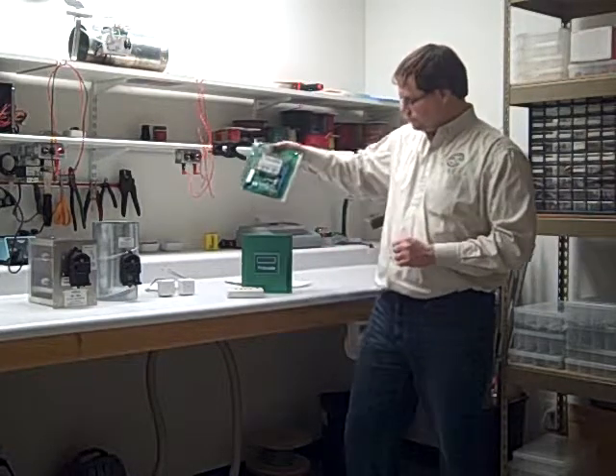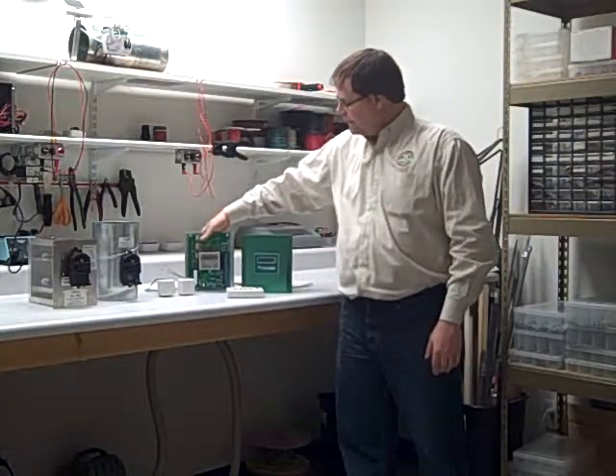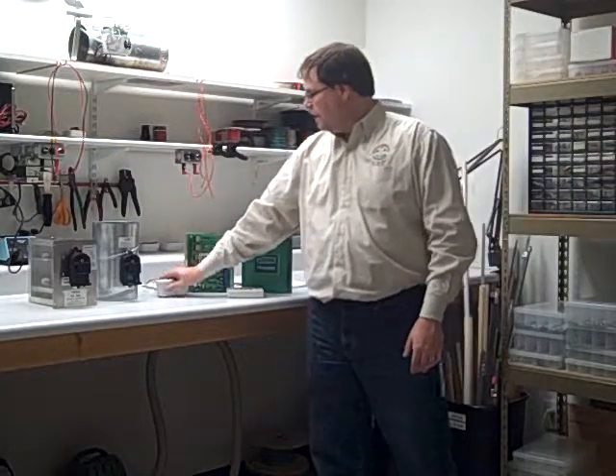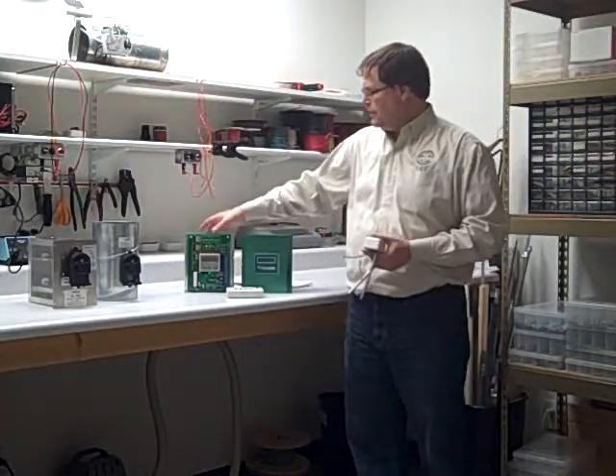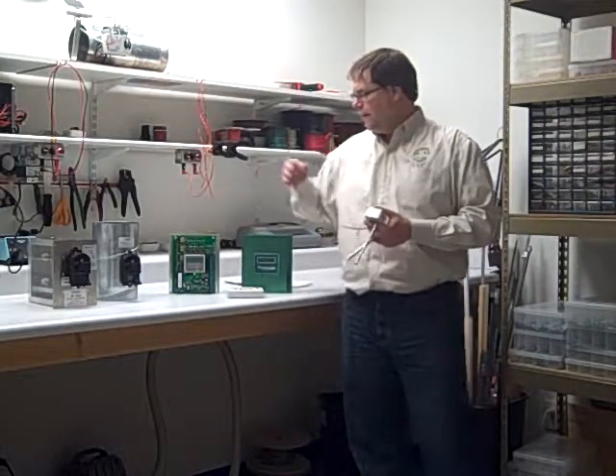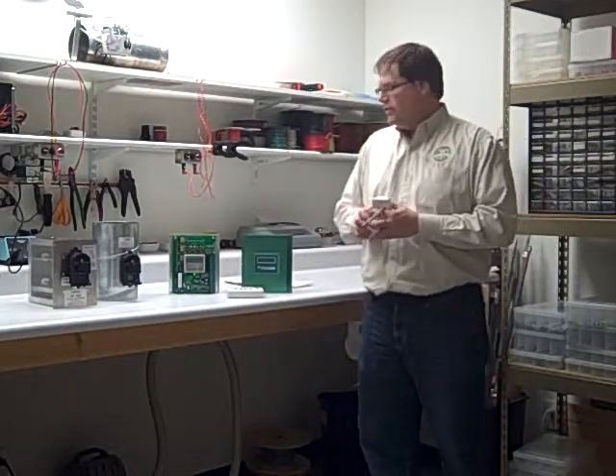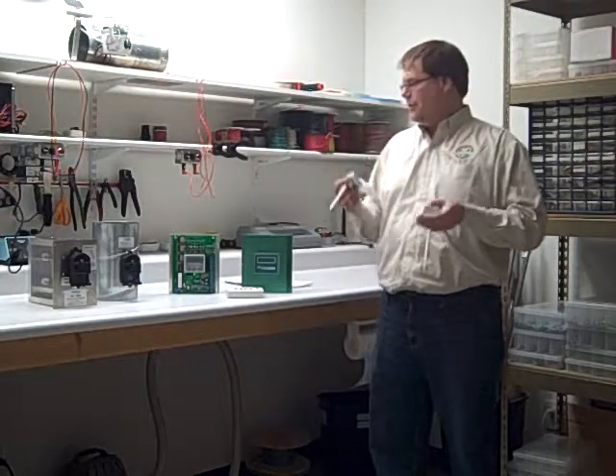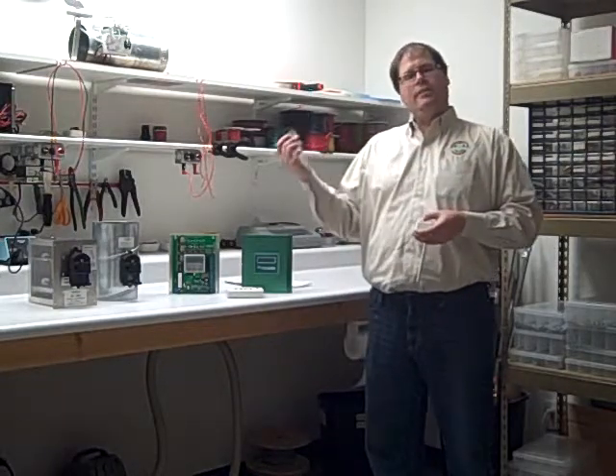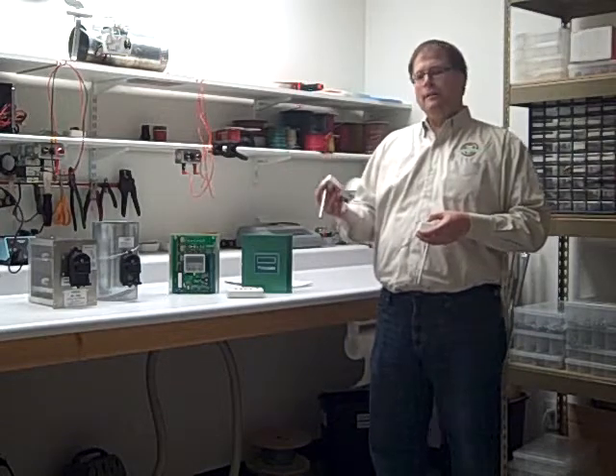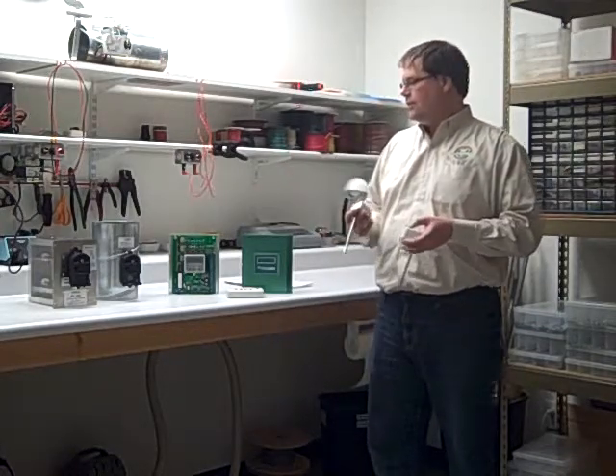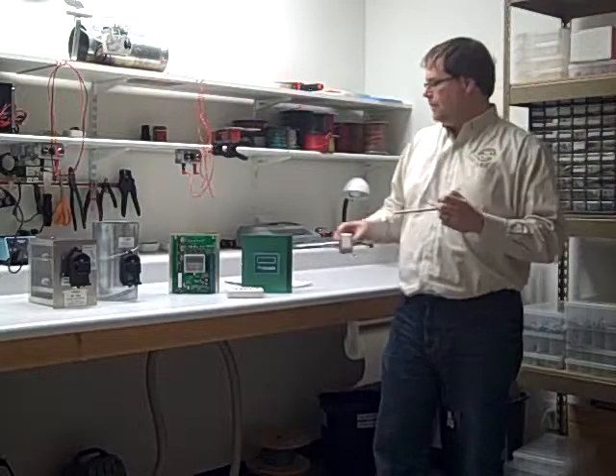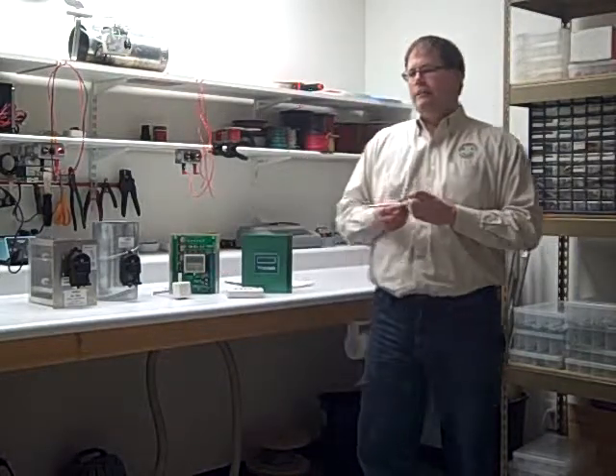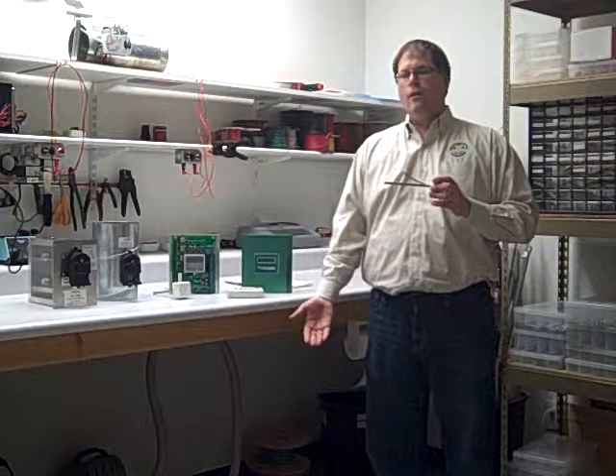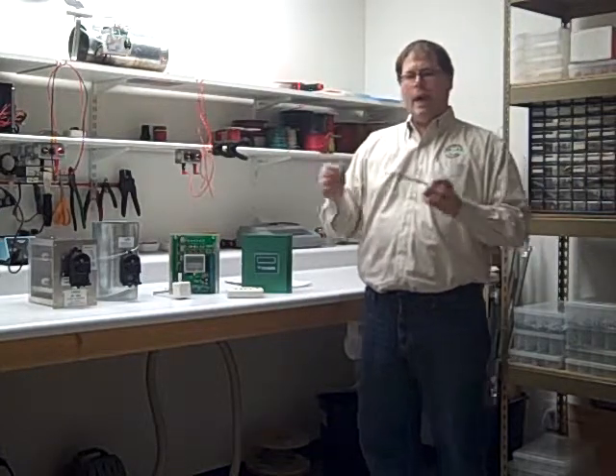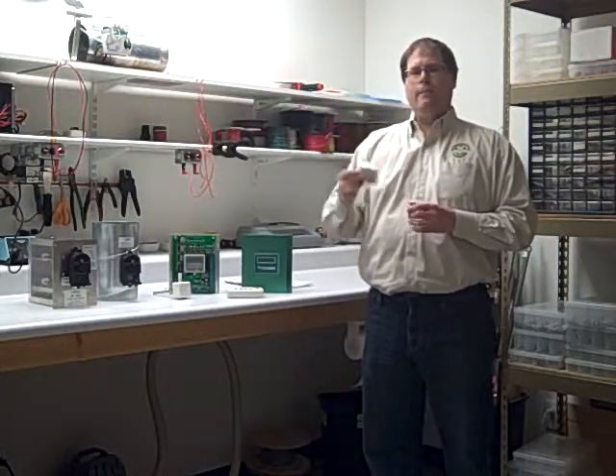Something new we've done with the wireless system is, because if all the thermostats were to stop communicating, we wanted to build in a level of additional backup protection. So we have 2 sensors that come with the panel. Every time you order a panel, you're going to get both of these sensors. We have both a discharge air sensor for high and low limit control like you're used to on any zoning system, but we also have a return air sensor with built-in temperature. So if the temperature starts to fall too low or gets too high because something wacky happens, this would kick on the equipment.